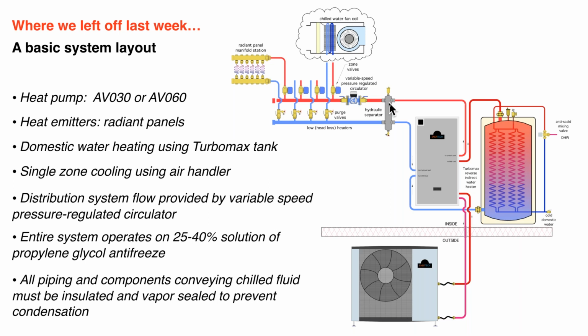But one of the things that separator is doing is providing our air venting. So we're taking the dissolved air bubbles that are in that water initially and getting them out of solution. We'd like that hydronic system to have the minimal amount of dissolved air content. Then to the left of the separator, you'll see a state-of-the-art distribution system. This is a variable speed pressure regulated circulator. I'll show you several products that you can use today for that. And then farther over here, these are zone valves.